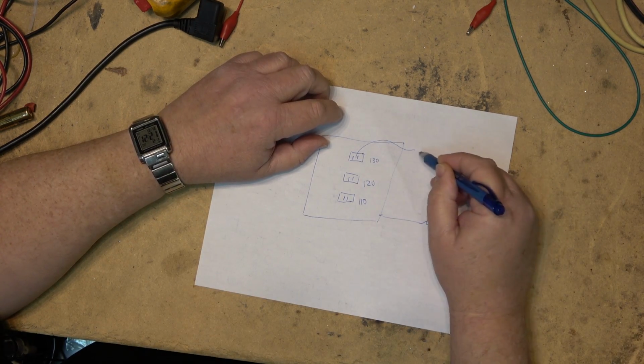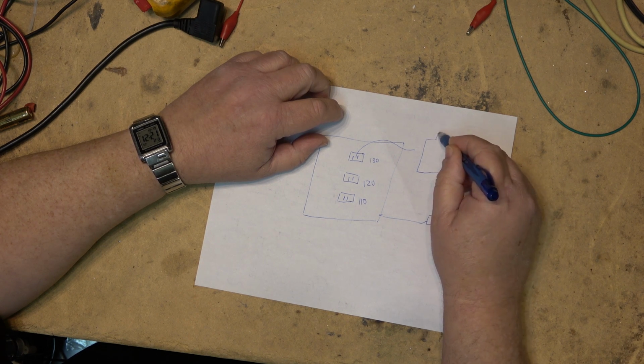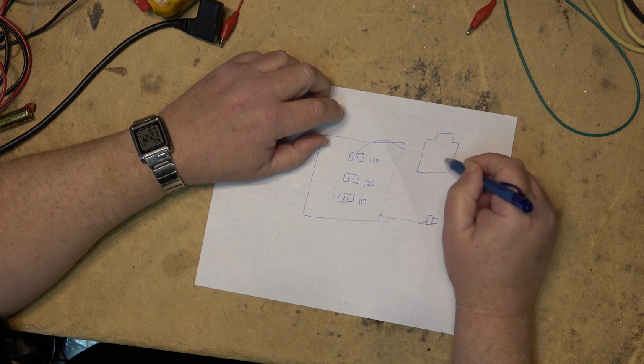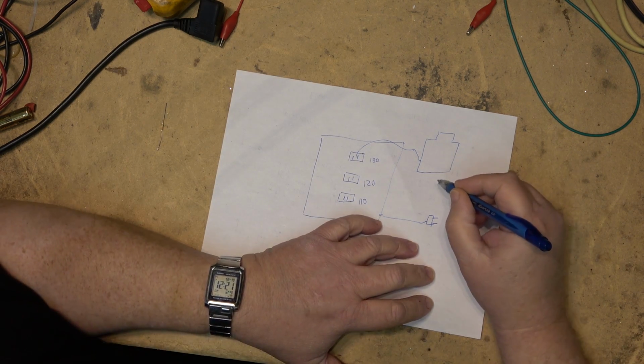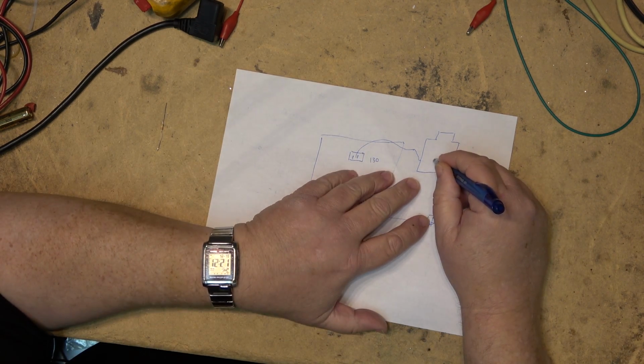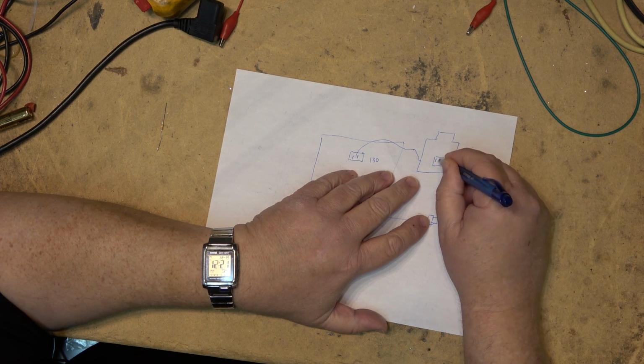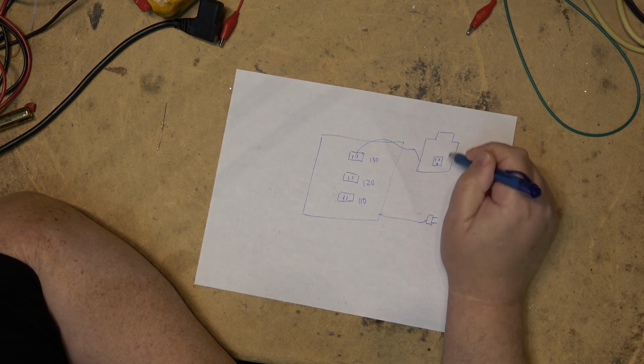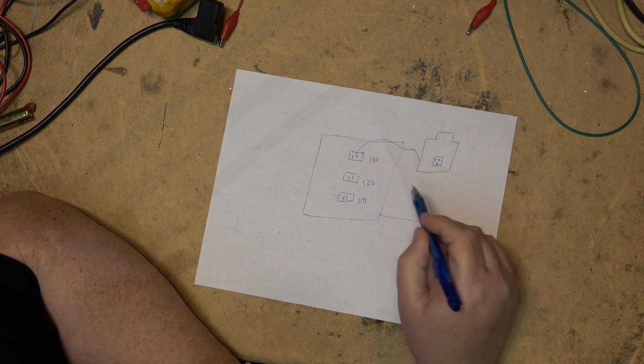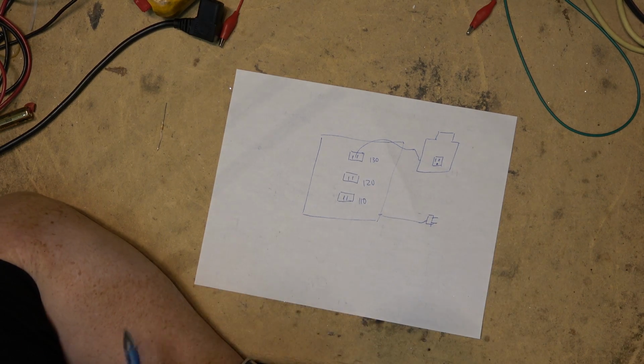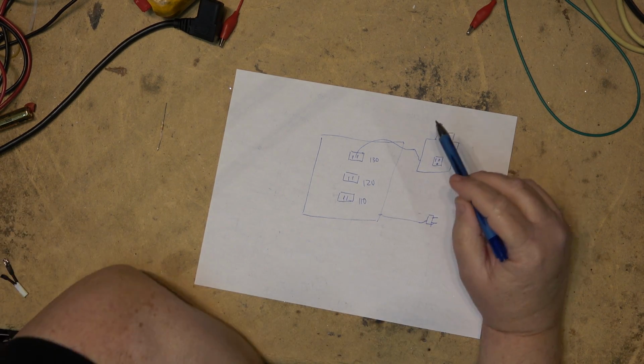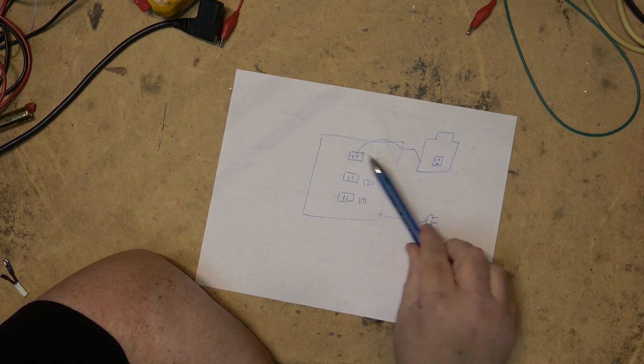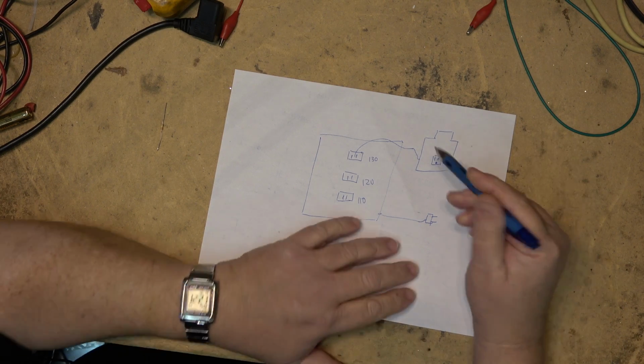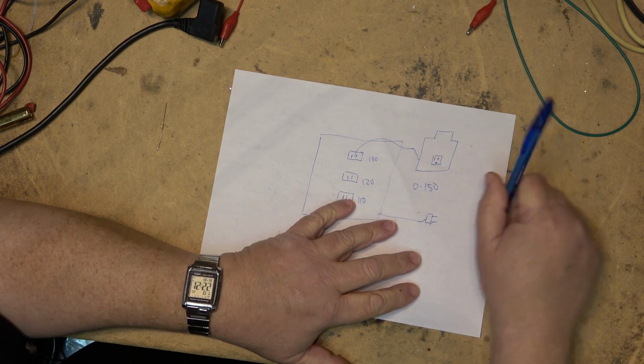I'm plugged into this one. This one goes off to my Variac. That goes off to my Variac, and it also has an outlet, but I had to cut the 3rd prong off to plug it into there, because it is completely isolated as well, because obviously a 3-prong outlet will not plug into that. But that's my setup. The reason I've done that is because the Variac would normally allow you to turn it between about 100 and 130 volts or so, but by giving it 130 on the input, I can go from 0 to about 150. I believe that's what I can get off of it.